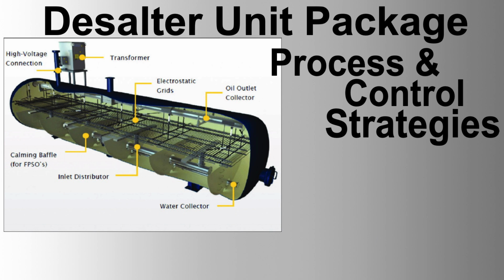3. Pressure control loop. Pressure transmitter PT301 measures the pressure inside the desalter vessel. Pressure controller PC301 maintains the desired pressure by adjusting the crude oil inlet valve, PV301. 4. Electrostatic field control loop. Voltage controller VC401 regulates the voltage applied to the electrostatic field to ensure effective coalescence of water droplets.